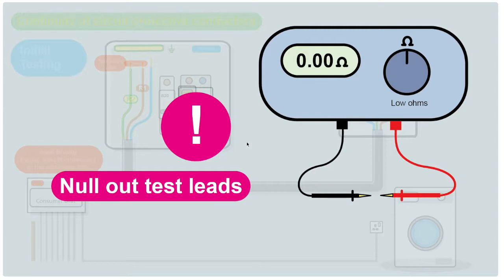It's important before we start doing any metered tests that we've nulled out our test leads. Nulling out is removing the resistance from the probes. If we put these probes together and press the test button we get a reading. We don't want that reading adding to any testing we're doing.